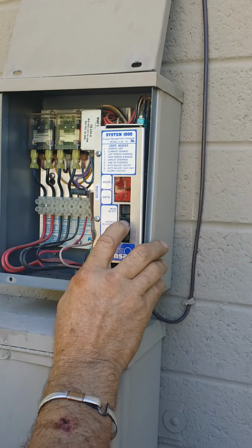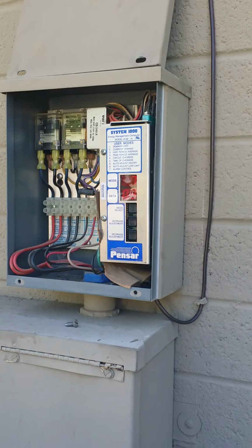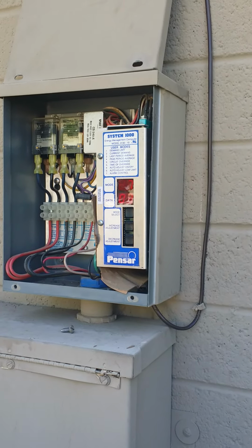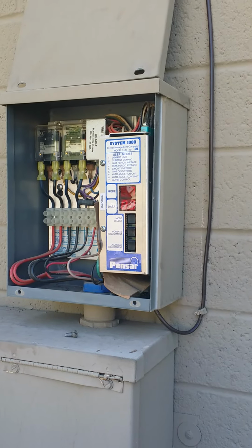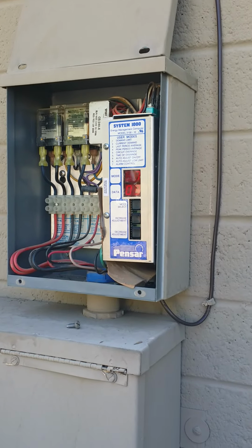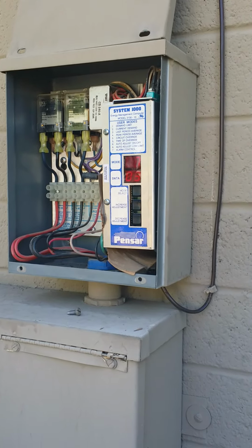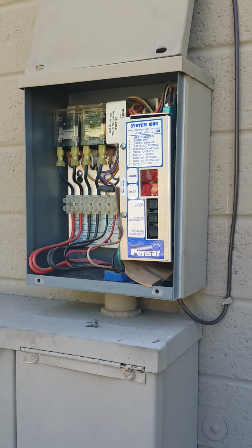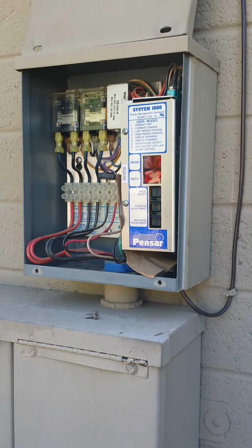But the only time the alarm is going to go off is if whatever it's connected to is shut off and you're still using more than what the load controller is called for. You should never hear the alarm, because the way this thing works, you've only got 3 loads. Does it sound inside or outside? Just outside. So you can't hear it anymore. Right. By the time the alarm goes off, the water heater, clothes dryer, and the air conditioner should be shut off. So you have to have 7,000 watts of somewhere else running, maybe like a big air conditioner in the shop, a welder in the shop, something that's not controlled that would make this go over the peak demand, because it's all on the same meter.